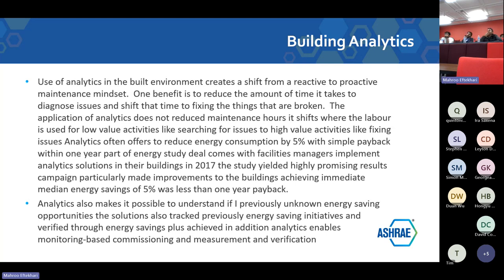The use of analytics in the built environment creates a shift from reactive to proactive maintenance opportunities. One benefit is reducing the time it takes to diagnose issues and shifting that time to fixing the problem. Applying analytics doesn't reduce maintenance hours, but it can reduce energy consumption because you catch things that are out of line in time to save energy. Analytics also makes it possible to understand previously unknown energy saving opportunities, and previously known opportunities can be tracked and verified through energy savings plus additional analytics needs.